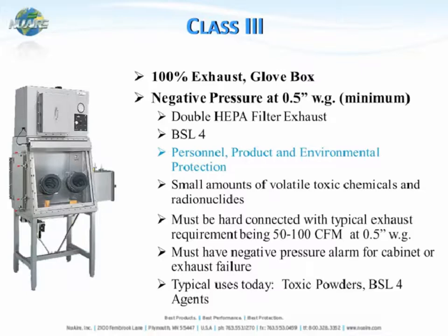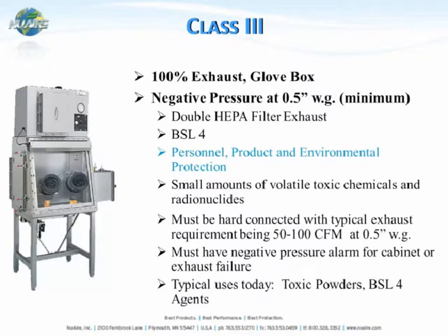The last biological safety cabinet is a Class III, also known as a glove box. These are 100% total exhaust, maintained under negative pressure at a minimum of 0.5 inches of water gauge static pressure. They're double HEPA filtered and are typically used only in BSL-4 laboratories for toxic powders and BSL-4 agents — not in the common everyday cell culture or tissue culture laboratories.